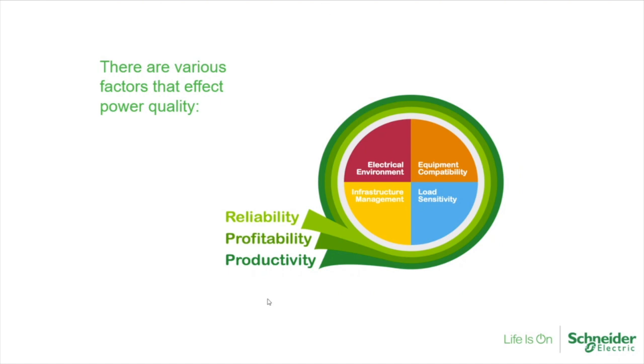And then there are various factors that affect power quality. It can come down to the electrical environment, equipment compatibility, making sure that you have the right rated equipment for your operation, and load sensitivity. Something I've noticed more with newer customers when I was at AEP, especially with newer equipment that has computers, it has more nonlinear loads. It's more sensitive to sag-swell events, to where in the past older equipment might have been able to ride through a plus or minus 10% sag or swell, where now the load is more sensitive and small variations can cause them to trip off. And then also infrastructure management. Well, we're looking at reliability, profitability, and productivity.